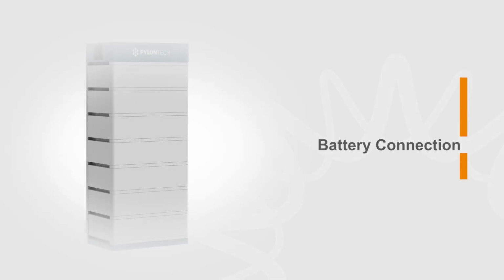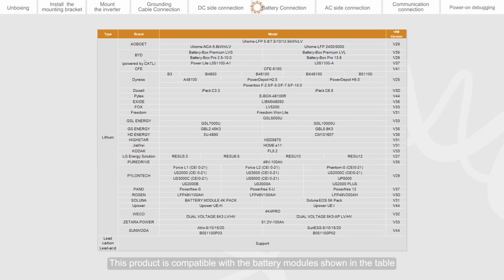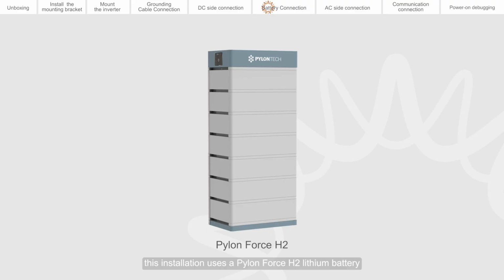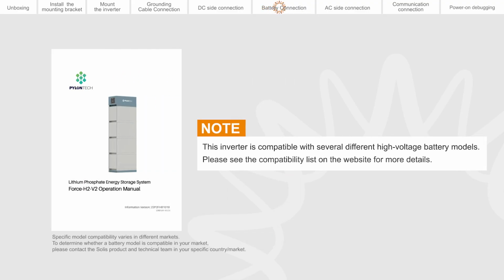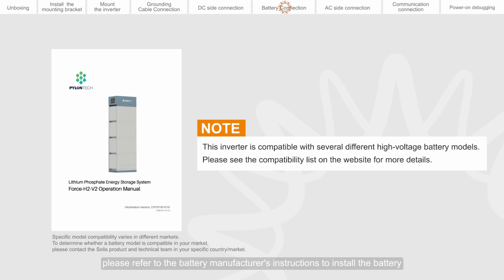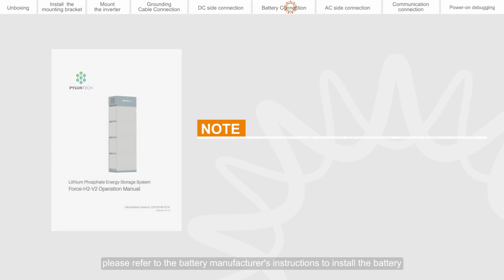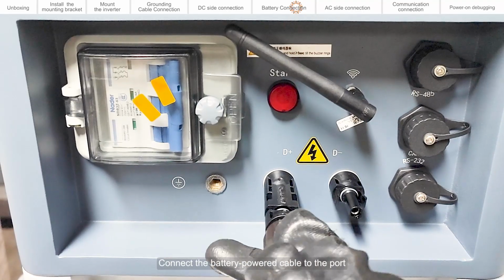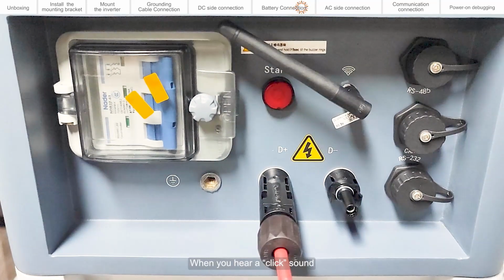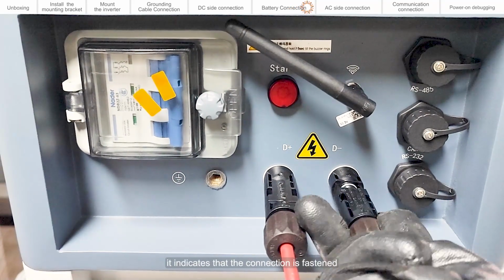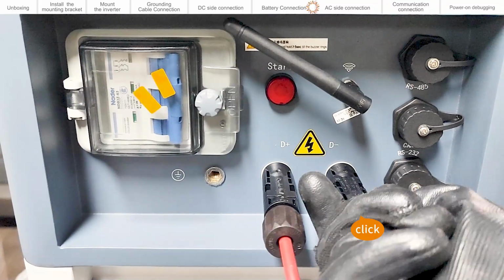Battery connection. This product is compatible with the battery modules shown in the table. This installation uses a pylon force H2 lithium battery. For battery installation, please refer to the battery manufacturer's instructions to install the battery. Connect the battery power cable to the port. When you hear a click sound, it indicates that the connection is fastened.